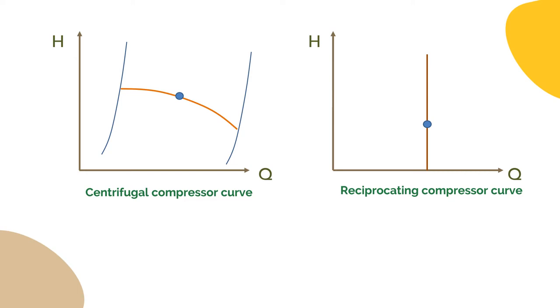For a pump, the pump head has a simple relationship with the differential pressure as the liquid density is constant. But for a compressor, and as gases are compressible, we shall have a more complex relationship as the gas physical properties change with the change of pressure and temperature.